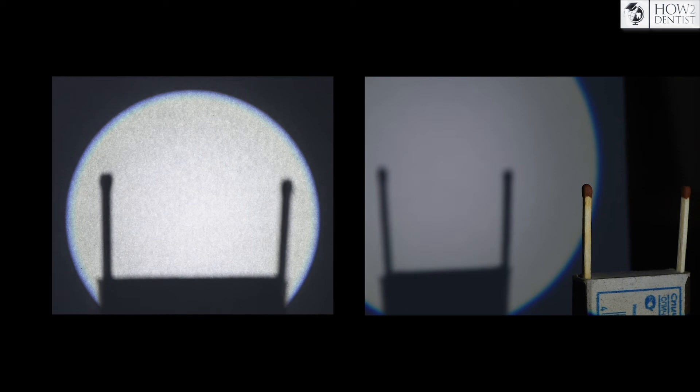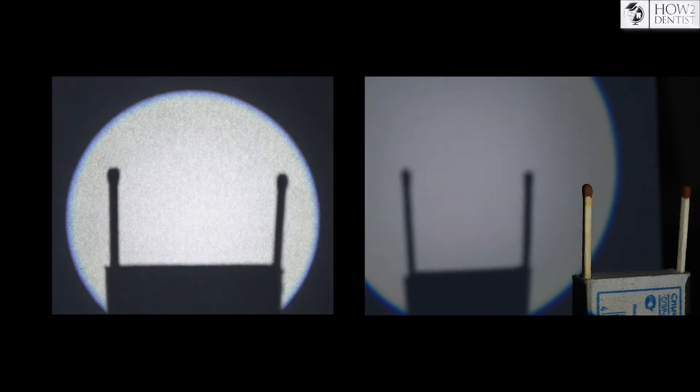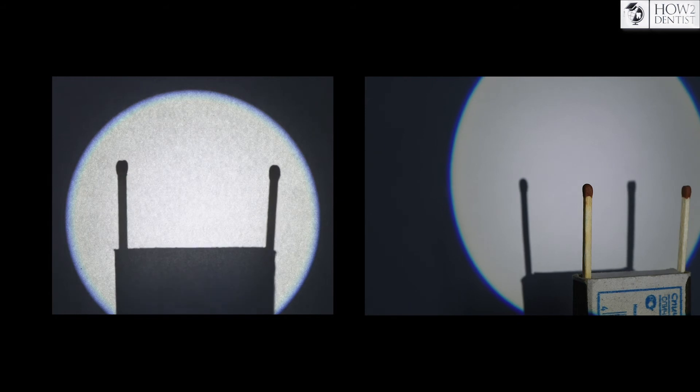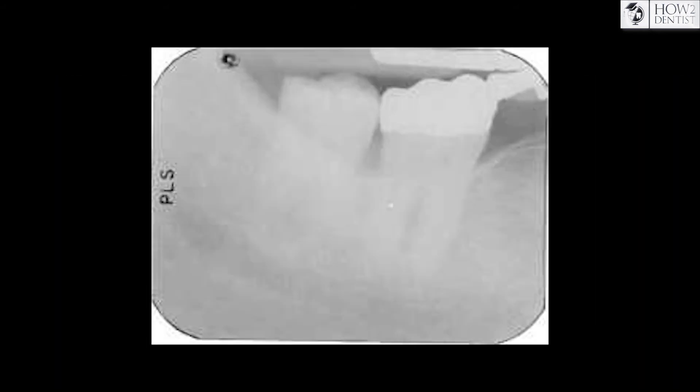The recommendation to place the sensor as close as possible to the tooth can also be illustrated by our example. When the sensor is moved back, the sharpness begins to decrease. In this example, you see a scan where the sensor is too far from the tooth.